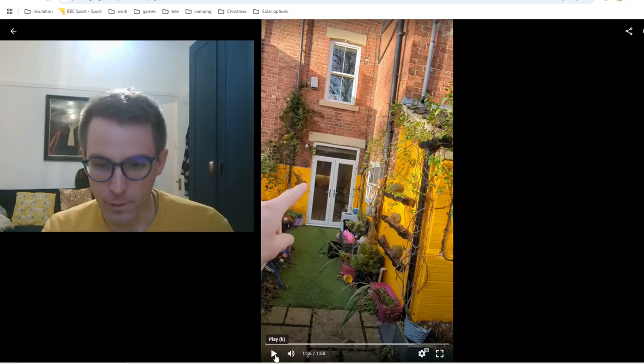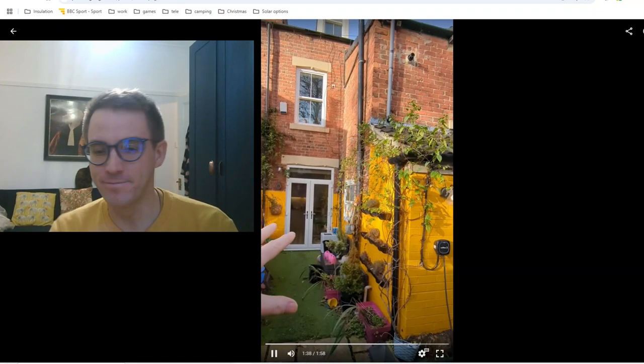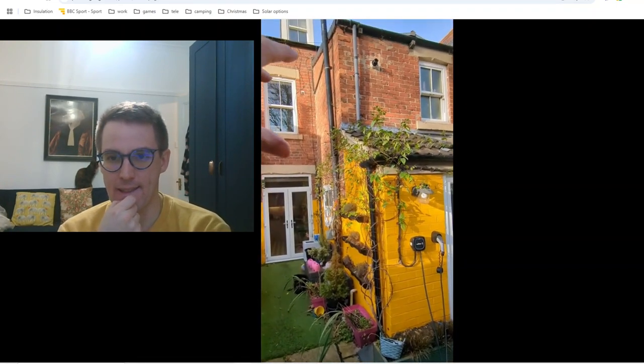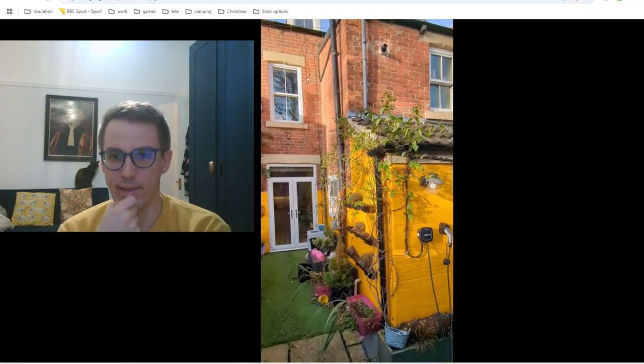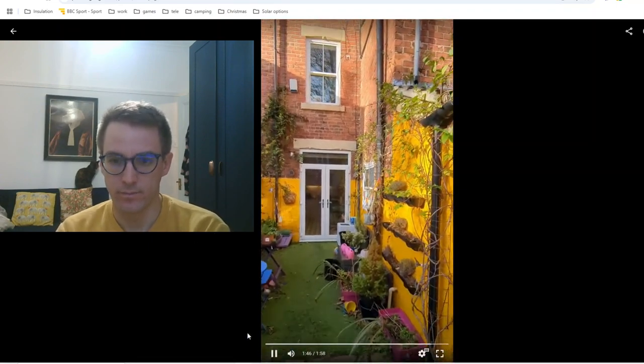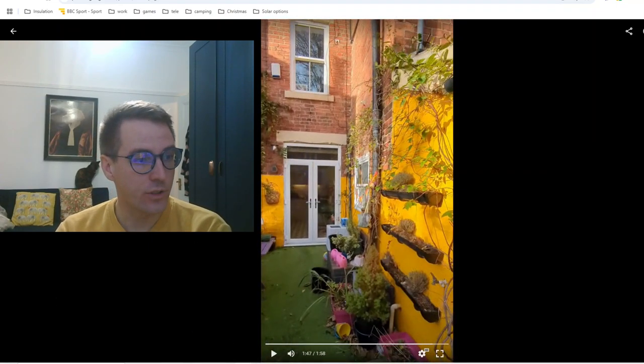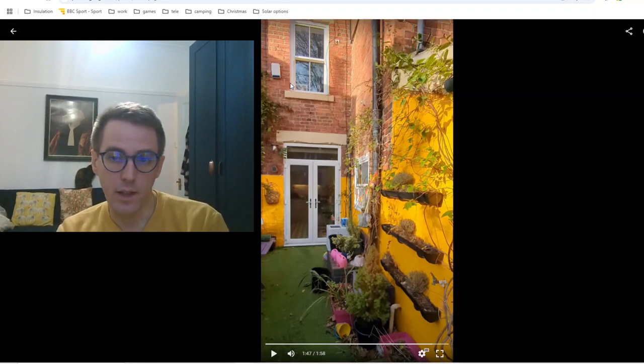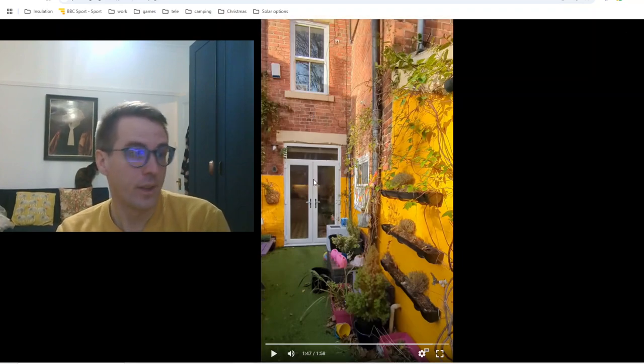And we're back. The heat loss is higher on the bottom floor because of the suspended ground floor, and the middle is only 2 and the top's only 2, so adding up to 9 or 10. The suspended floor means that you leak heat out into the void underneath, and that's not connected to another floor. This top room will be leaking heat into the bottom of the house, but that's fine, because that's within your house, so it doesn't matter.